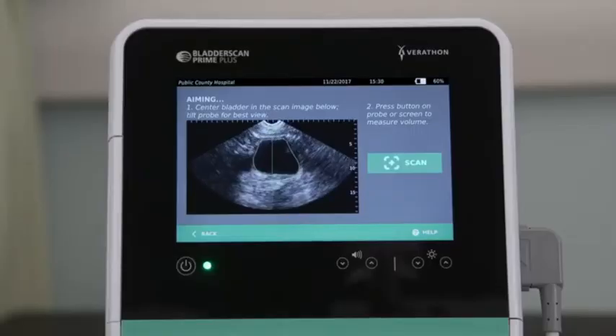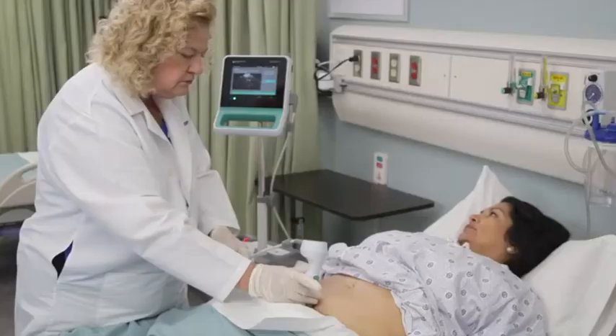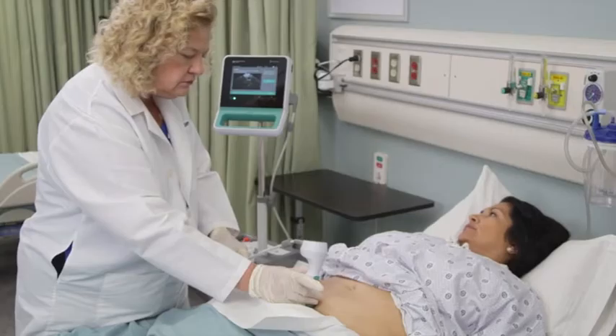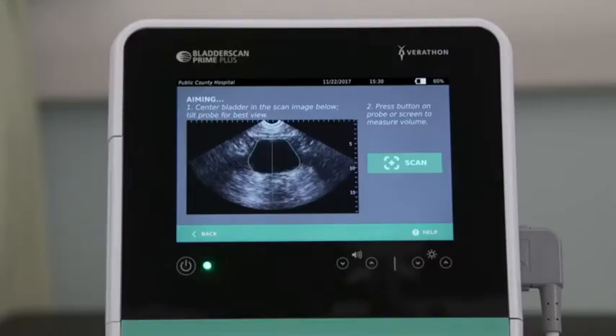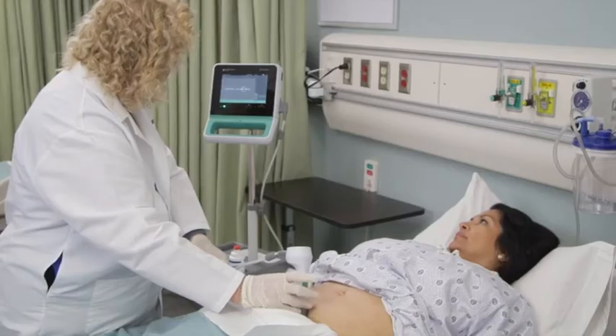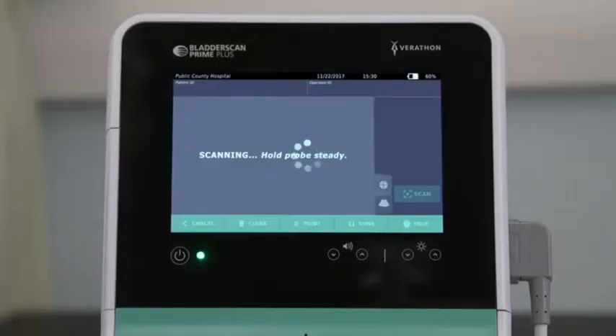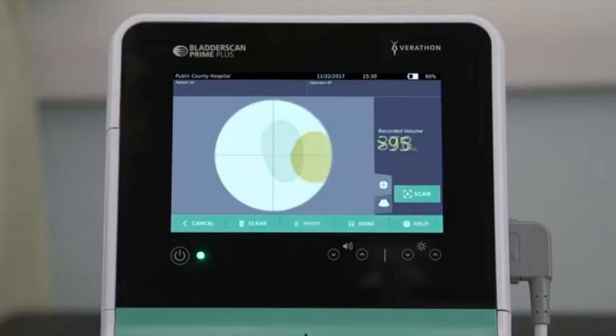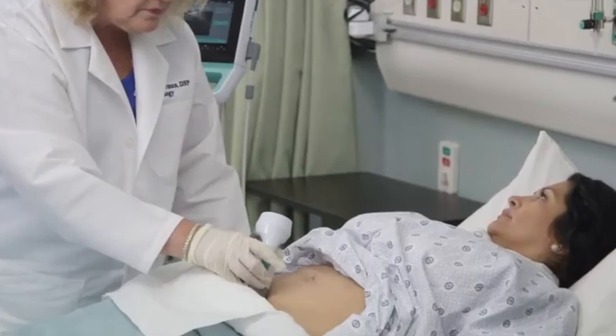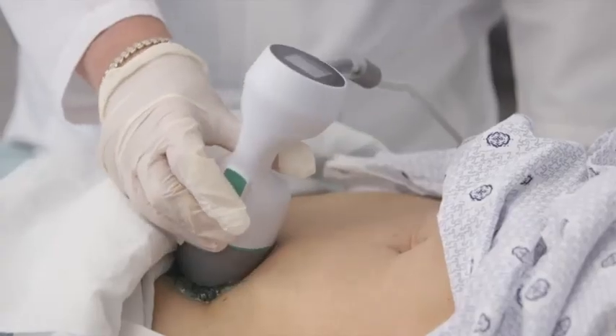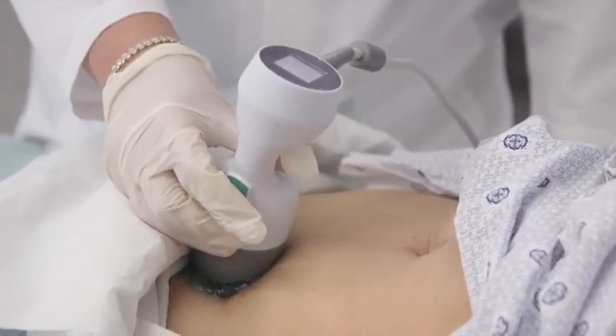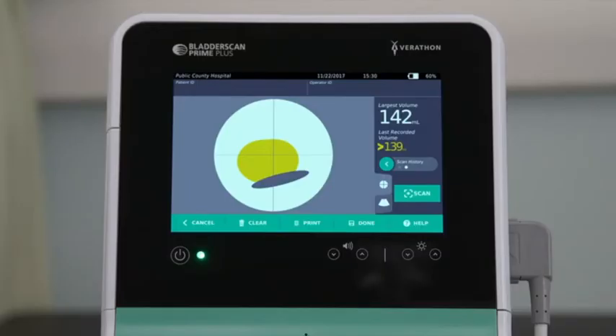Move the probe slowly, using the bladder track feature to center the bladder on the screen. To begin the scan, press and release the scan button or tap Scan on the touch screen. Hold the probe steady while the scan is in progress until the volume results are displayed. If the bladder icon is off-center, re-aim the probe, pointing it in the direction indicated to maximize the bladder image. If the scan area indicates pubic bone interference, an icon will appear. Reposition the probe above the pubic bone and rescan.